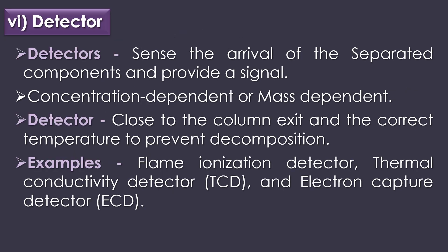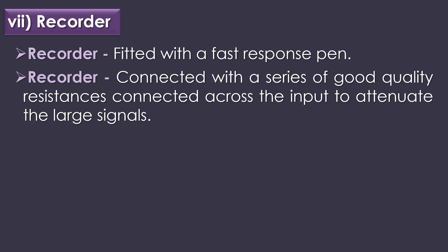The sixth part of gas chromatography is detectors. Detectors sense the arrival of the separated components and provide a signal. Detectors are either concentration dependent or mass dependent, and should be close to the column exit at the correct temperature to prevent decomposition. Common examples of gas chromatographic detectors are the flame ionization detector, thermal conductivity detector, and electron capture detector. The seventh part is the recorder, which should be fitted with a fast response pen of one second or less, connected with a series of quality resistances to attenuate large signals.